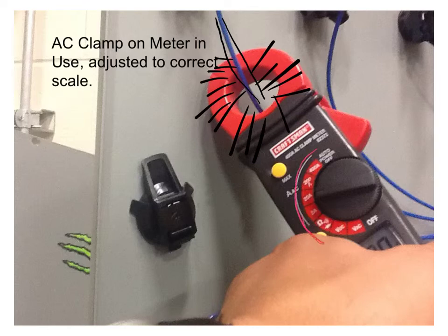We've used our ranging feature here. In this case, I've got the dial turned to the 20A, so this right now is capable of measuring 20 amps if we needed to go that far. And if we got to the point where maybe we were under 5 amps, maybe then we would want to go ahead and readjust and get down to the 2 amp range. And if it kept going down, we'd have a little more accurate measurement then using that meter.